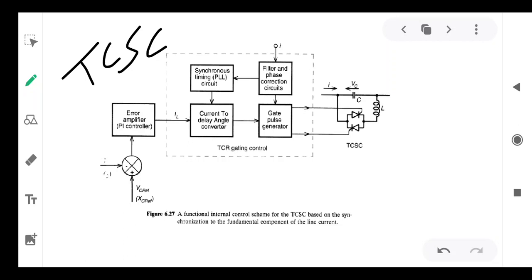TCSC is somewhat superior to both GCSC as well as TSSC. The harmonics of the TCSC can be reduced by splitting TCSC into a number of capacitor banks and one capacitor anti-parallel with TCR combination, so that the TCR current can be very small and injected harmonics are negligible.